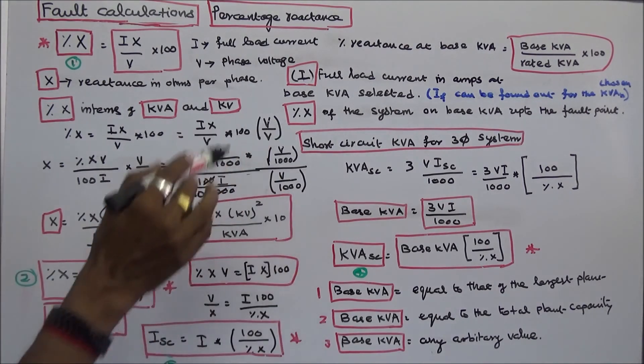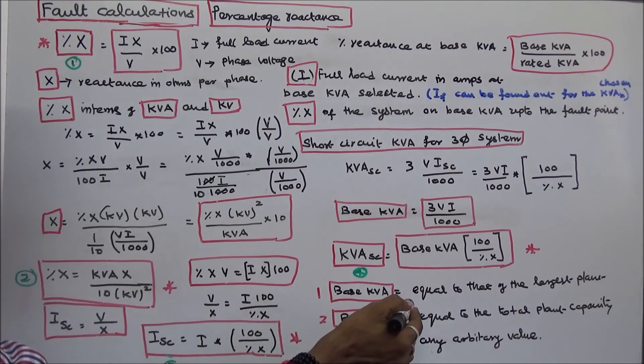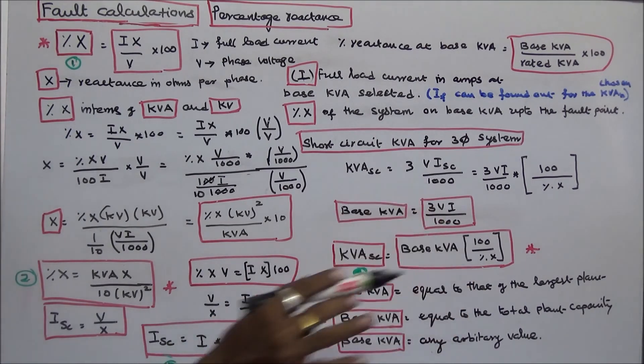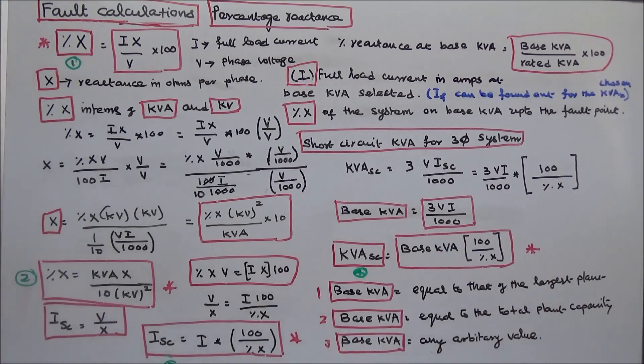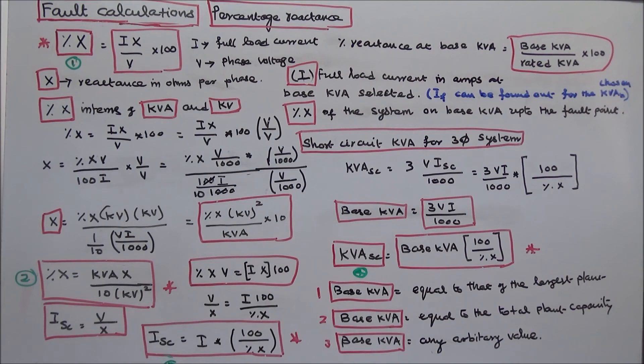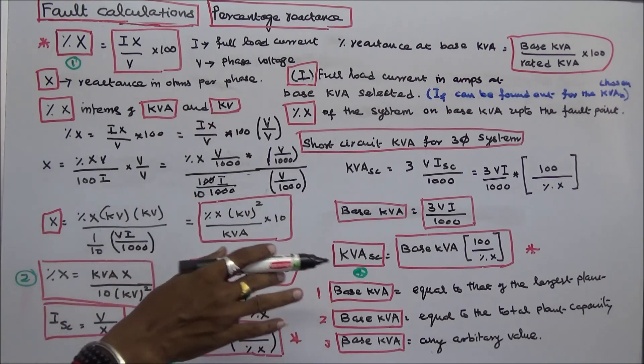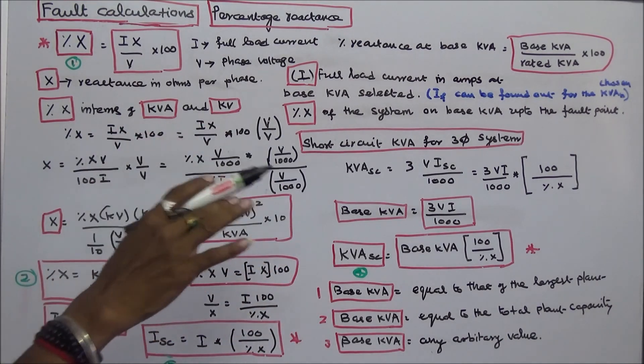To select a base KVA, there are three options. First, base KVA can equal that of the largest plant. Second, base KVA can equal the total plant capacity. Third, base KVA can be any arbitrary value. Using these methods, we calculate percentage reactance, which is very useful for finding short circuit current and short circuit KVA.